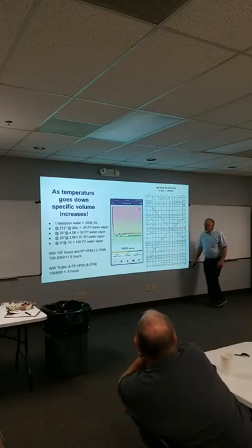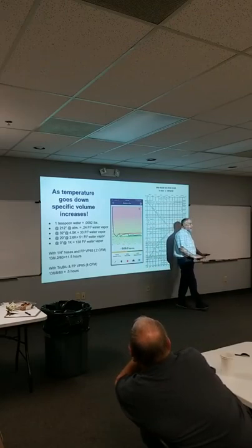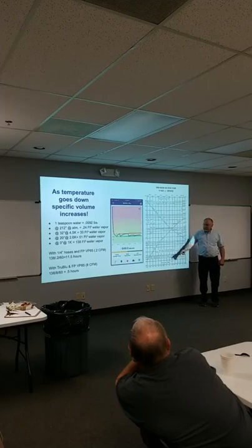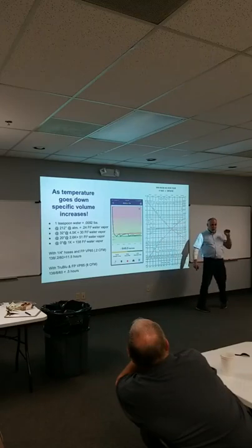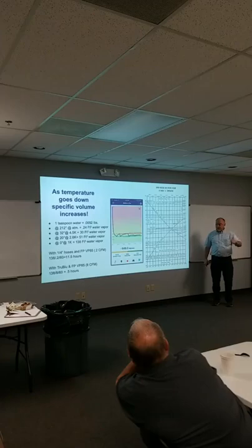The other thing I want to show you here, and the reason this one's so important, I have a ton of guys in the industry who say, I hit 500 microns, I valve it off, and it's good enough. Well, I hit 500 microns on that graph 1, 2, 3, 4 times, and that system's sopping wet. Because every time I valved it off here, you see this fast rise in the curve. When it curves off like this, that indicates it's tailing off as it's building up a vapor pressure, and it's eventually going to equalize.